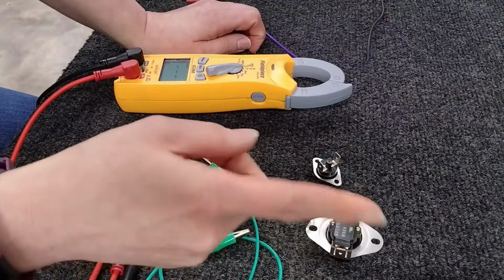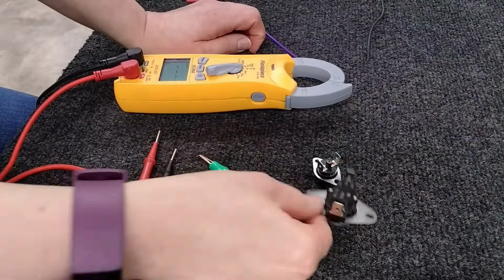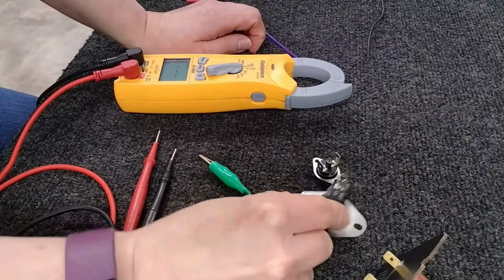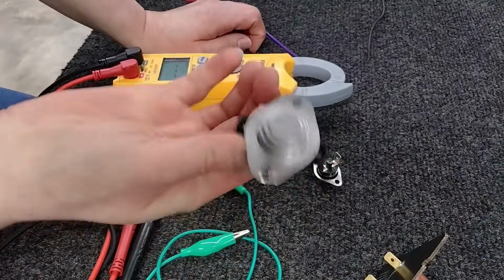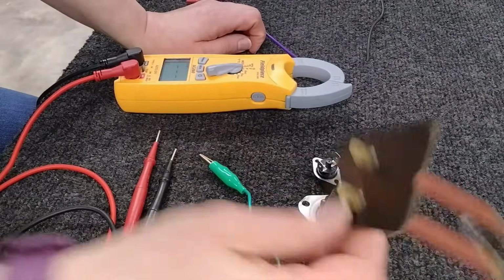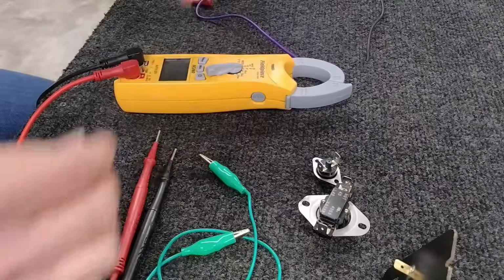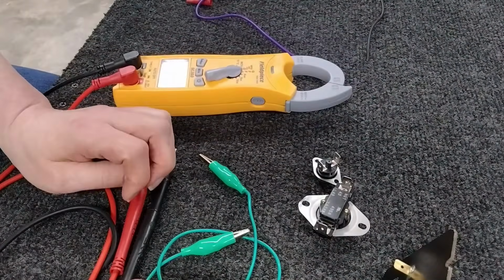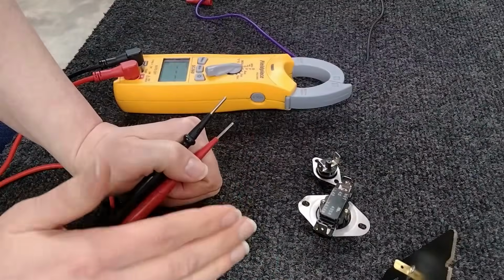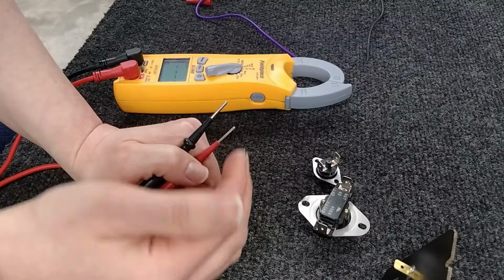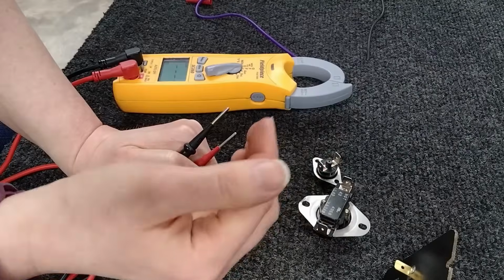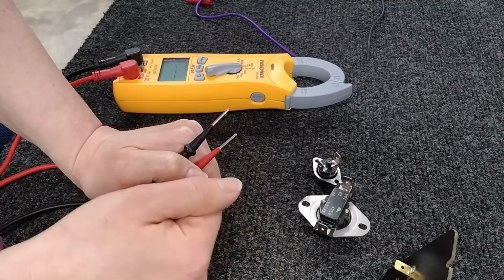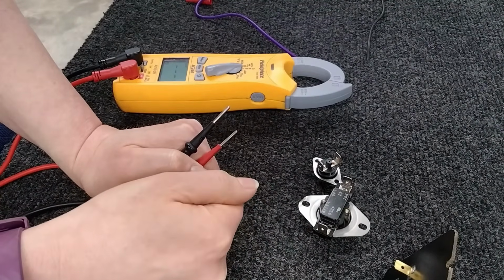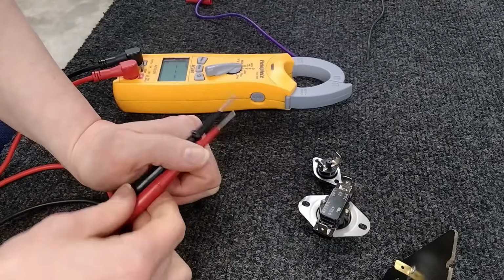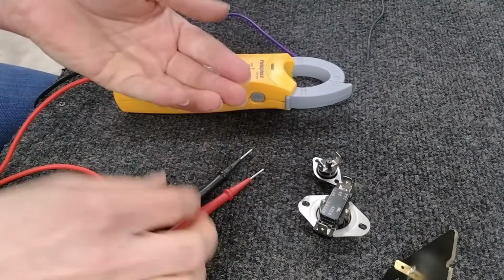Bypass this one, bypass your limit switch. Usually this is secondary, but some primaries can look like this. Bypass your high limit. And do what you need to do systematically, one by one, to find that bad limit switch. Once you think you've found the culprit, you can take it one step further just to double check that it is actually that limit switch. And I'm going to show you how. And bonus, you get to play with fire.